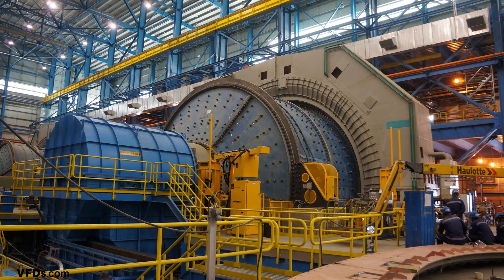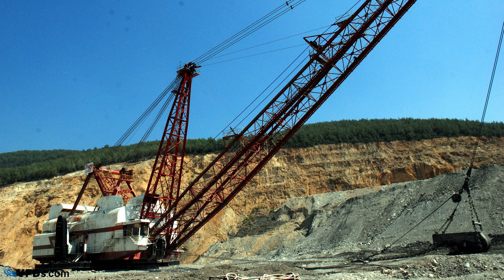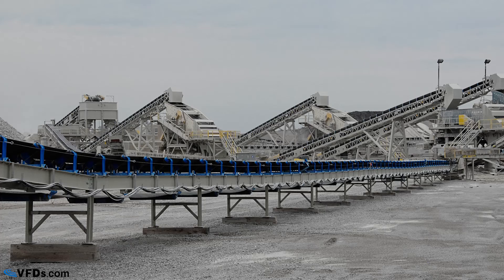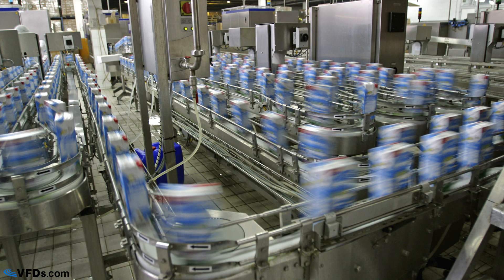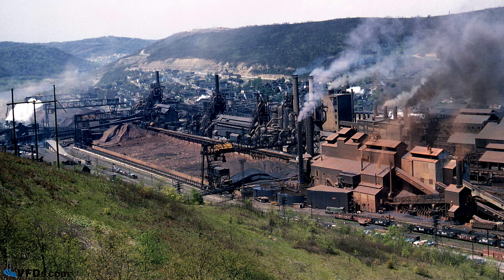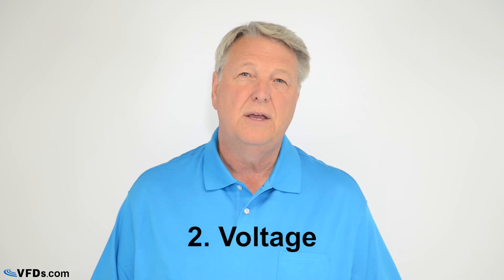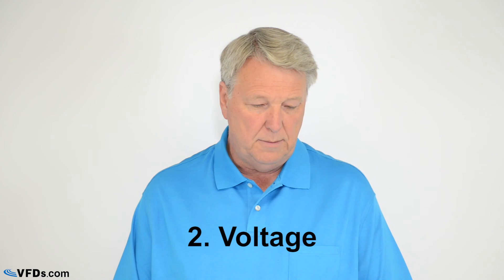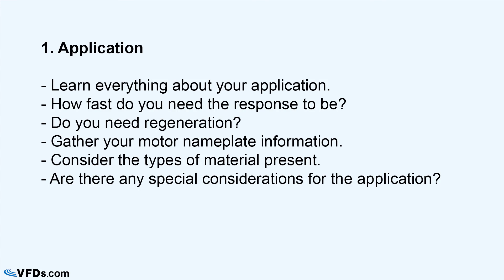The application means what is the motor driving. Examples include a mine hoist, a grinding or ball mill, a shovel or drag line excavator, an overland conveyor, or material handling. The most difficult applications are things like fully integrated steel mill drives. Each requires different types of drives and different types of engineering experience. Learn everything about your application: how fast does the response need to be, do you need regeneration, what is the motor nameplate, what type of materials will be present, and what special considerations apply?